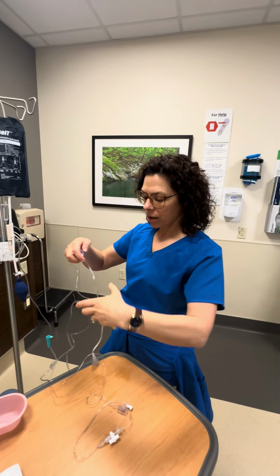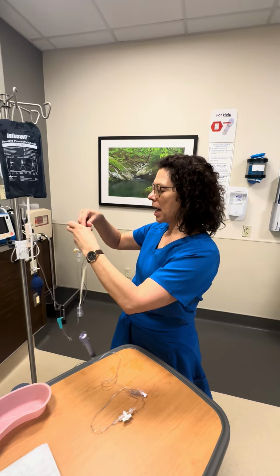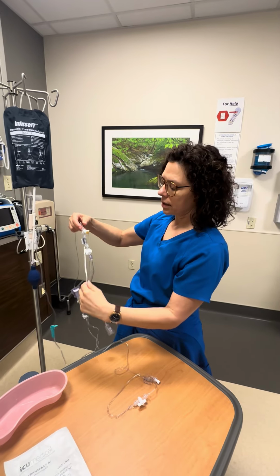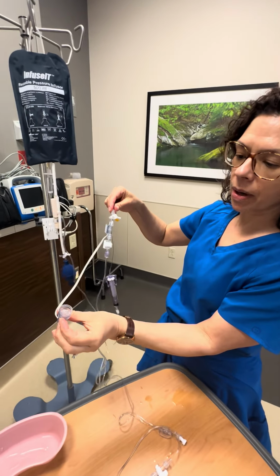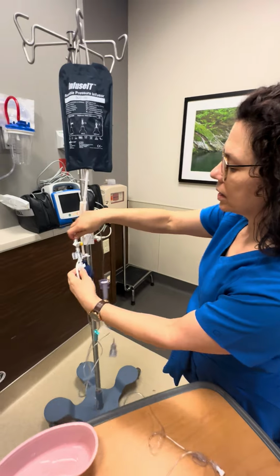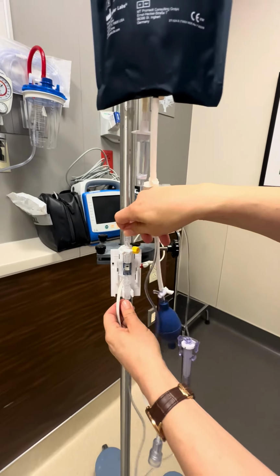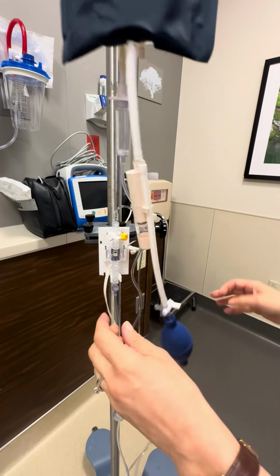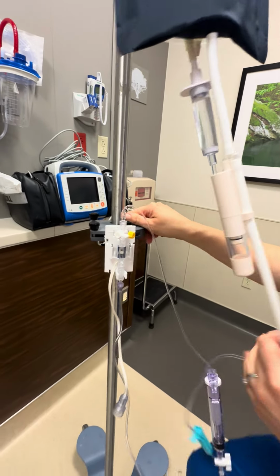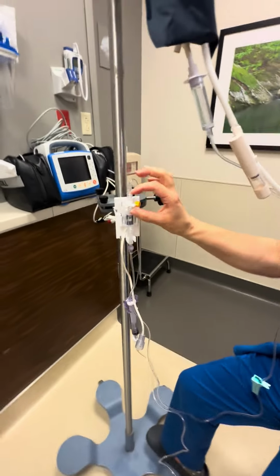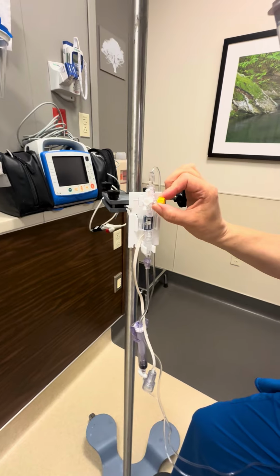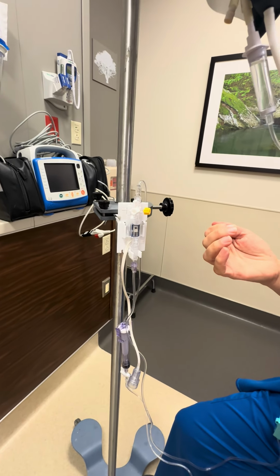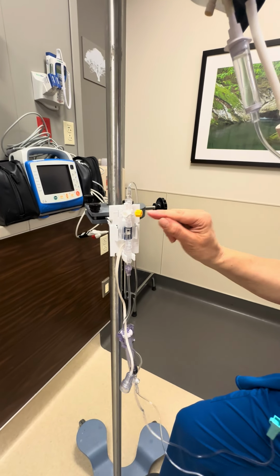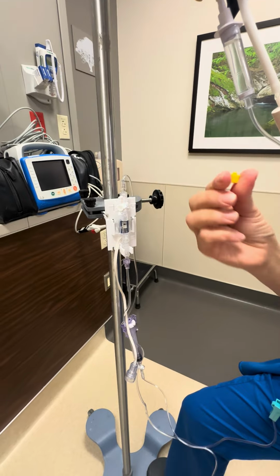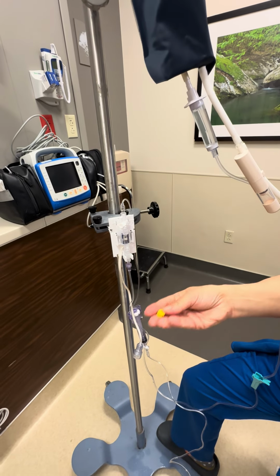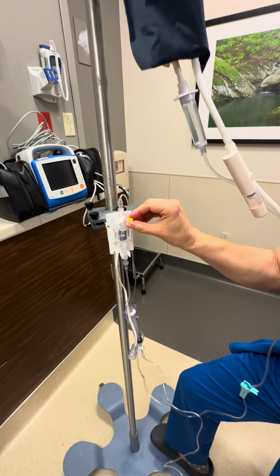So after you spike your bag and you open up your pack, the way you're going to place this is you're going to have the tail, the part that connects to your monitors, arrowed facing towards down. So I like to say tail down. Inside your pack, because this is equipment from education, this actually will be a white cap that you can prime through. It's open for sterilization, so a little bit of water will squeeze out. This is the closed cap that once you're done priming, you will replace it with this cap.